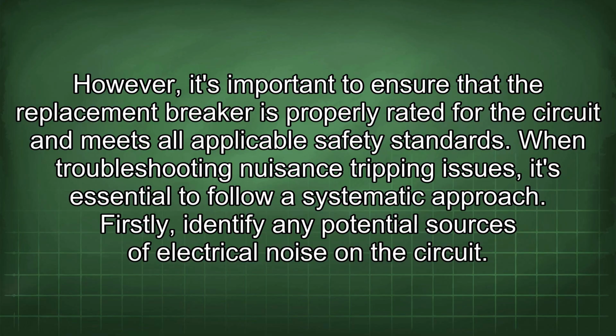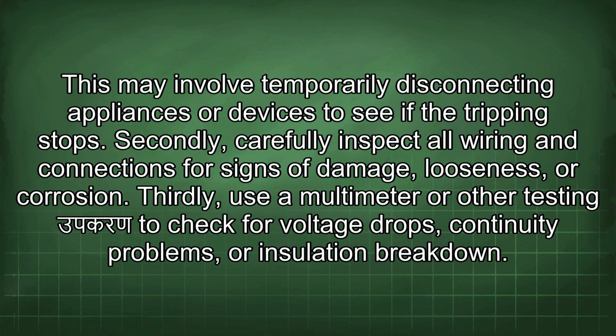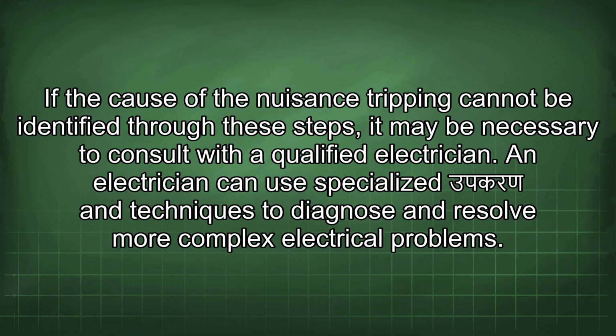When troubleshooting nuisance tripping issues, it's essential to follow a systematic approach. Firstly, identify any potential sources of electrical noise on the circuit. This may involve temporarily disconnecting appliances or devices to see if the tripping stops. Secondly, carefully inspect all wiring and connections for signs of damage, looseness, or corrosion. Thirdly, use a multimeter or other testing equipment to check for voltage drops, continuity problems, or insulation breakdown. If the cause of the nuisance tripping cannot be identified through these steps, it may be necessary to consult with a qualified electrician. An electrician can use specialized equipment and techniques to diagnose and resolve more complex electrical problems.